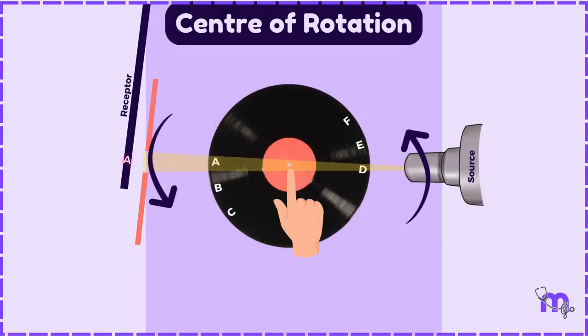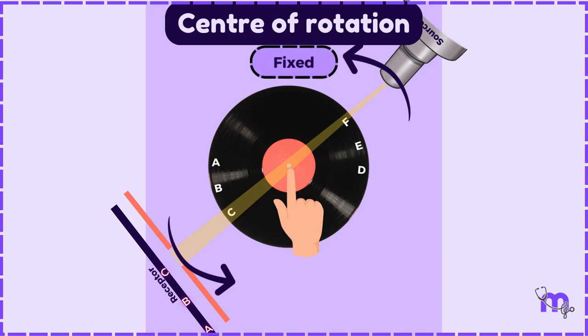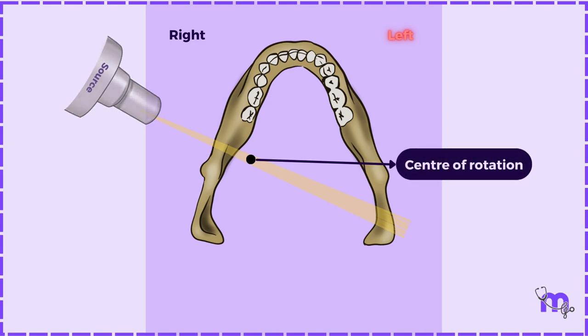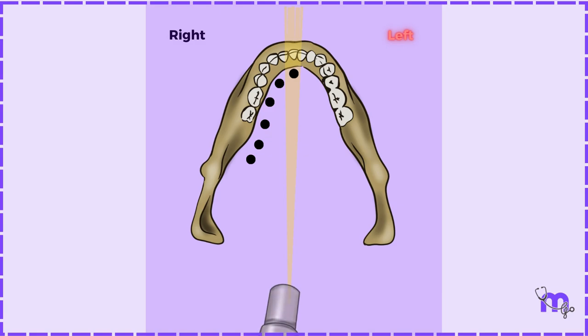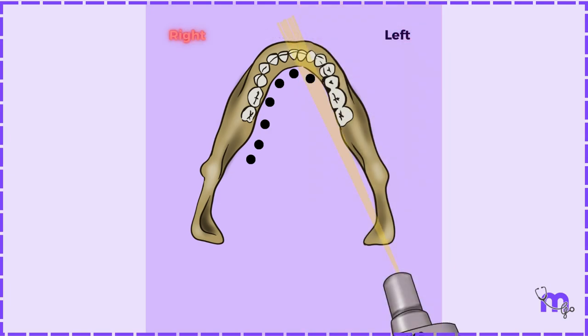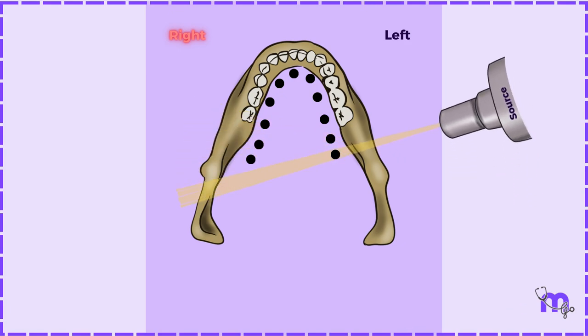Let us now discuss the center of rotation. While we studied the working principle of the panoramic machine, we noticed that the center of rotation remained fixed. But contemporary machines use a continuous moving center of rotation. If X-ray exposure begins from the left side of the arch, starting from the condyle and extending diagonally opposite, the center of rotation would be located on the posterior lingual aspect of the right side of the mandible. As the X-ray source rotates, the center of rotation shifts along the shape of the arch. Multiple centers of rotation form along the lingual sides until, after completing its rotation, a panoramic image is captured.